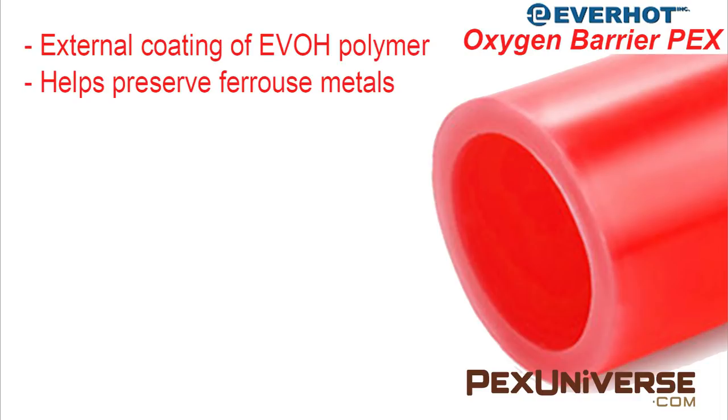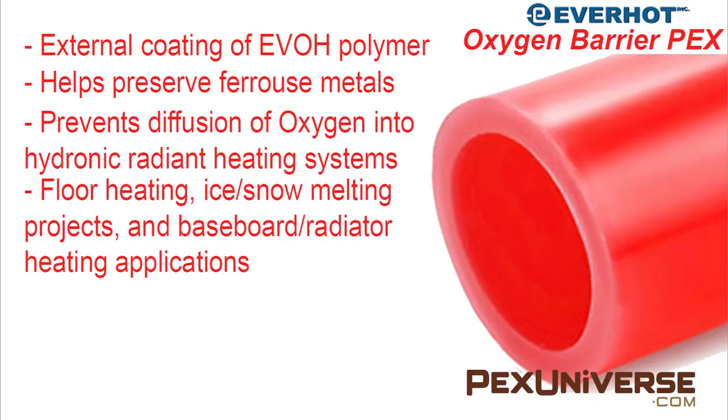Oxygen barrier tubing is used for radiant floor heating, ice and snow melting projects, and baseboard heating applications. It can also be used for supply and return lines to boilers and fan coils. It has a pressure rating of 100 psi at 180 degrees Fahrenheit. Oxygen barrier PEX comes in three-eighths of an inch, half inch, five-eighths of an inch, three-quarter inch, and one inch sizes.